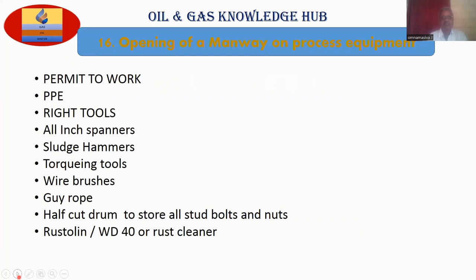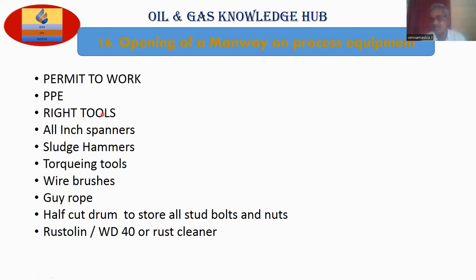What are the requirements? In the hydrocarbon area during shutdown activities, you should have conducted a site meeting prior to opening the manway. The team leader should discuss how to open it. Permit to work system is required. PPE. Right tools — specifically, you should use only inch spanners for inch bolts. You should not use millimeter spanners; it leads to accidents. The right tools are important.